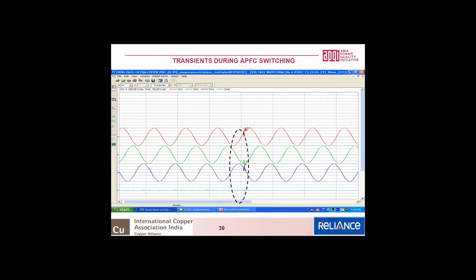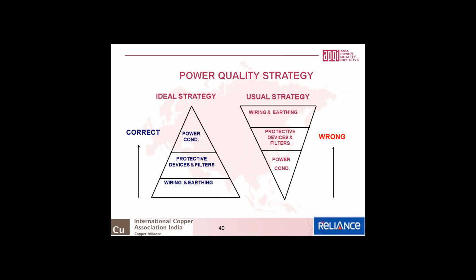This is the last slide. Whenever PQ problems are faced by a customer and referred to solution providers, the first instinct is to go for high and fancy solutions. But the problem could be due to simple wiring or bad earthing practices. Simply by improving shielding, earthing, or by providing isolation transformers like zigzag, many PQ problems can be resolved. If the problem still persists, then high-end solutions like surge suppressors, passive filters and active filters can be considered, but only as a last resort.